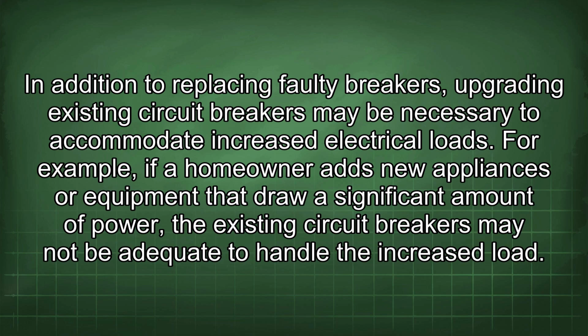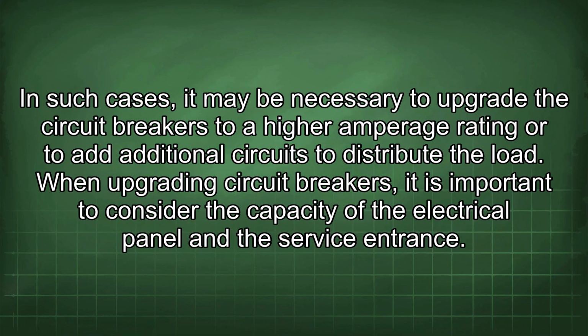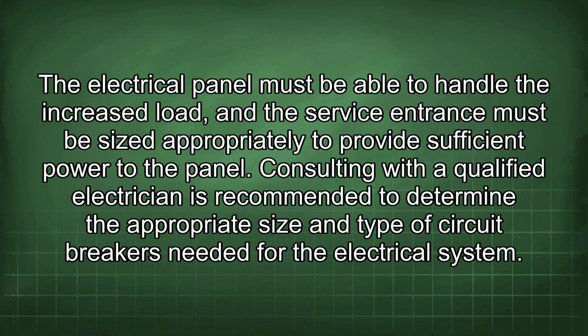For example, if a homeowner adds new appliances or equipment that draw a significant amount of power, the existing circuit breakers may not be adequate to handle the increased load. In such cases, it may be necessary to upgrade the circuit breakers to a higher amperage rating or to add additional circuits to distribute the load. When upgrading circuit breakers, it is important to consider the capacity of the electrical panel and the service entrance. The electrical panel must be able to handle the increased load, and the service entrance must be sized appropriately to provide sufficient power to the panel.